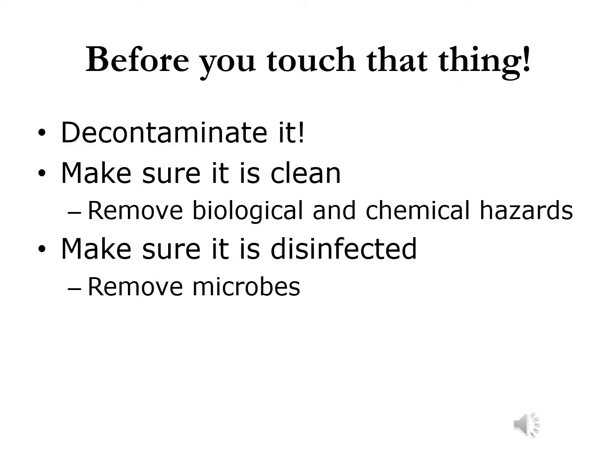So, to wrap up what we've just talked about, before you start working, before you touch that thing, decontaminate it. Clean off what's on it, remove the soil, and then make sure it's disinfected or sterilized, whichever, so that it's safe for you to work on and or for others to work with.